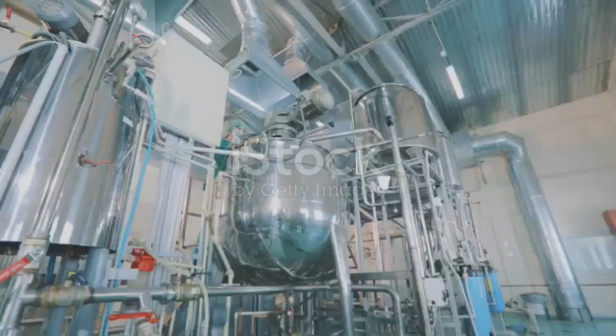Equipment qualification has real-world impact, especially in health-critical industries. Take an autoclave in a medicine factory. DQ checks the chamber's size and materials, IQ verifies installation, OQ tests controls and sensors, and PQ proves it sterilizes reliably using biological indicators.